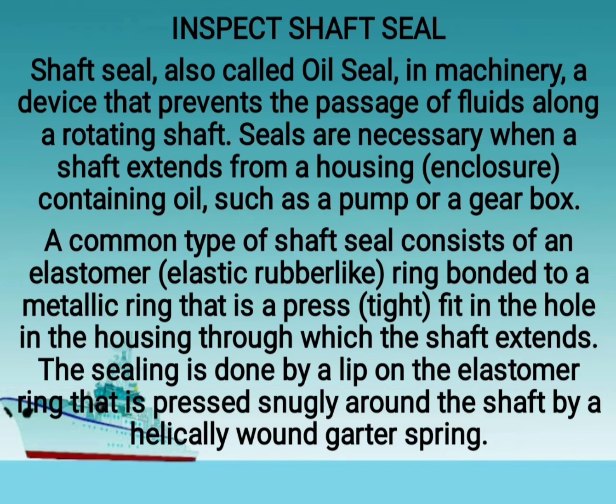Today I'm going to discuss inspecting the shaft seal. A shaft seal, also called an oil seal, in machinery, is a device that prevents the passage of fluids along a rotating shaft. Seals are necessary when a shaft extends from the housing enclosure containing oil, such as a pump or a gearbox. A common type of shaft seal consists of an elastomer, an elastic rubber-like ring, bonded to a metallic ring that is pressed tight-fit in the hole in the housing through which the shaft extends.